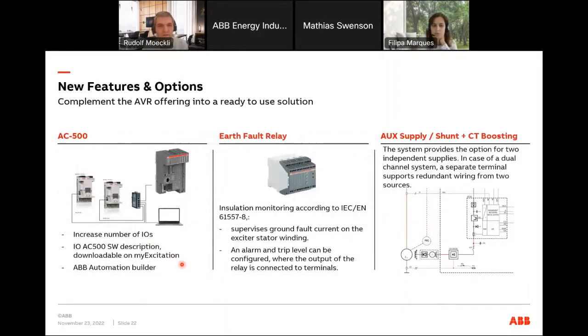So here comes the second slide, how it looks like with this AC500. That is actually the device, connected over Ethernet switch to both devices. It works in a way that you have the digital IOs - an input is fed into the AC500, then in parallel going to both devices. The AC500 will distinguish which of these channels are active and feed back an output signal. That's how it works, and it's pretty simple to change or adapt other signals to that.